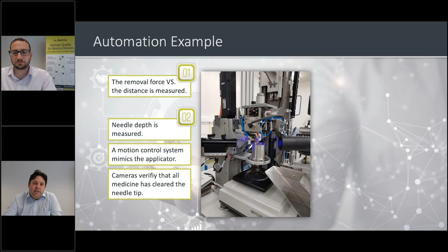A vibration actuator on the insert will release any droplets from the needle tip if required. Finally, the plunger actuator retracts and the total volume is verified by a scale. Once complete, the system verifies the safety needle shield is reapplied correctly and takes the appropriate next steps based on the results. For insert identity verification, the insert parameters are read from the RFID tag.